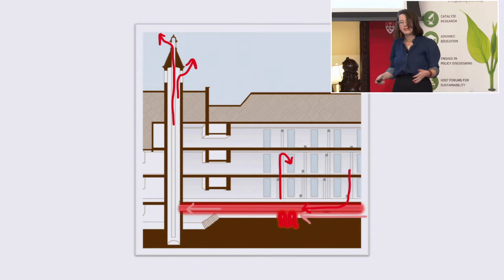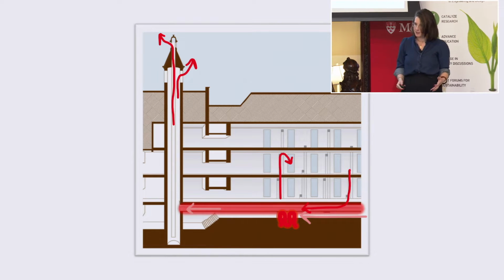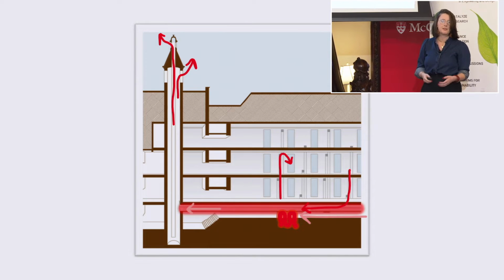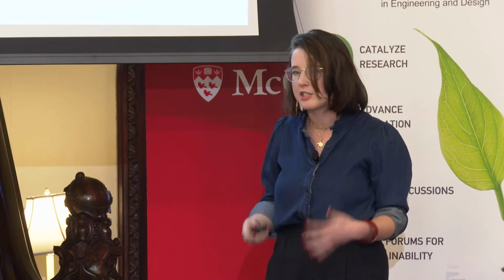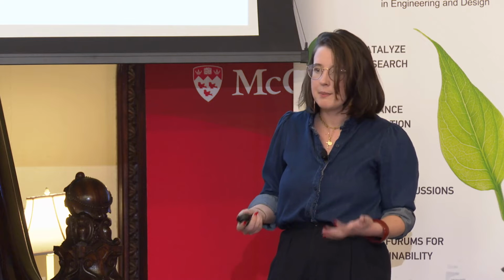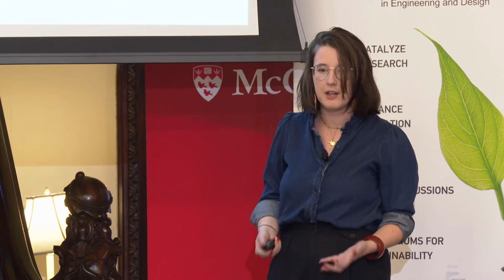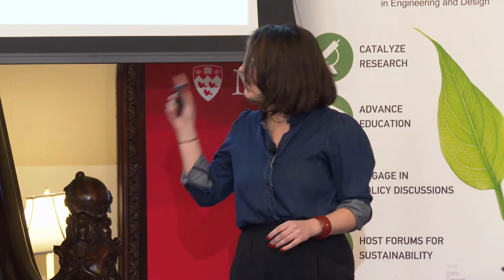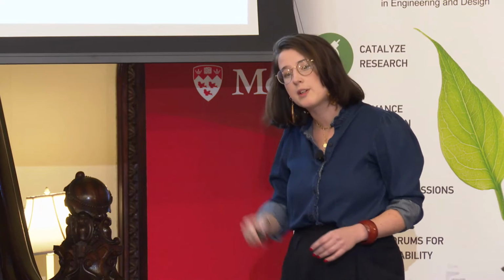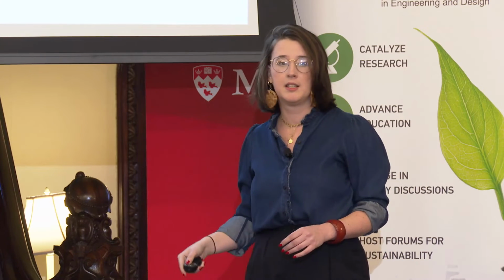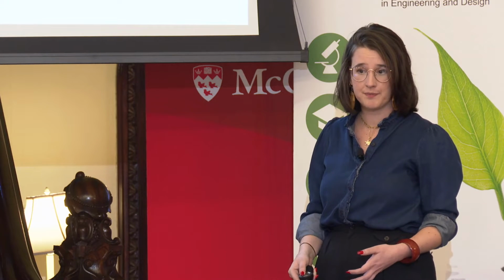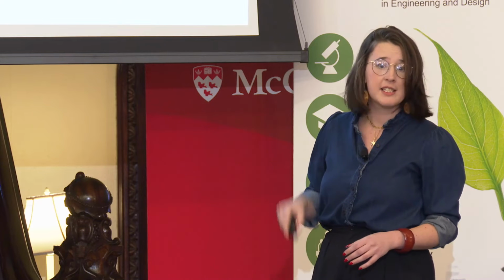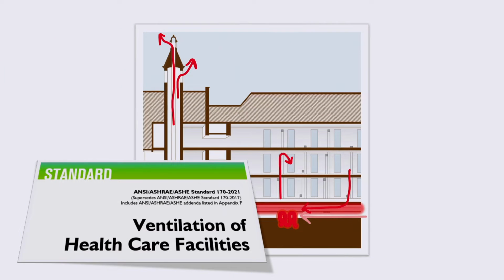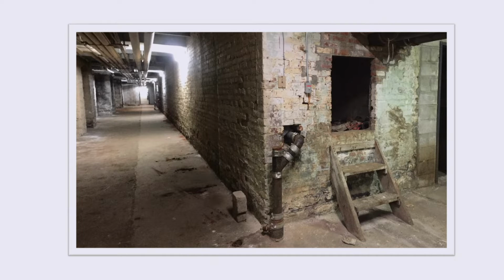We do estimate that the efficiency was probably low due to low performance materials of the time, but it didn't need to be much. Unlike modern high-performance heat recovery ventilation, this innovation wasn't focused on energy efficiency, really. It was just focused on keeping the pipes from freezing and maintaining a healthy ventilation rate for the hospital. And importantly, we've simulated that that scheme would have provided a ventilation rate of between 40 to 60 liters per second per person, or between 3 and 4 fresh air changes per hour. To put that in context, our current ASHRAE standard for patient rooms in hospitals is 4 air changes per hour. And they're doing this with one of the earliest examples of heat recovery known today.